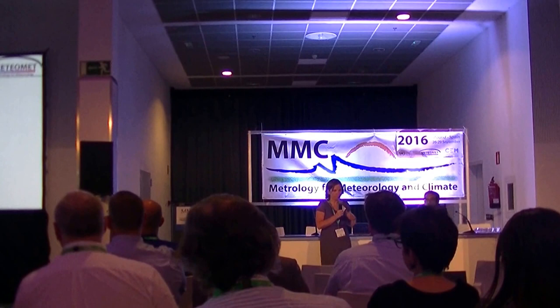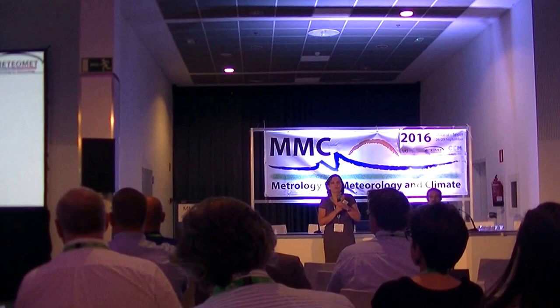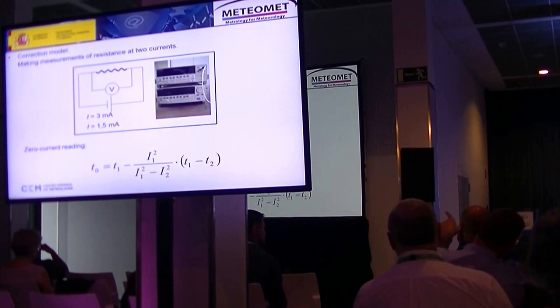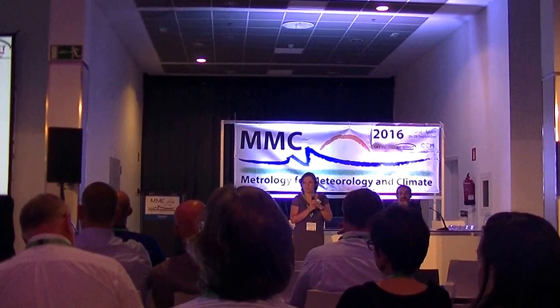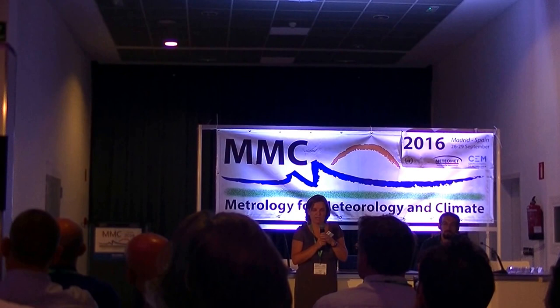The correction model used to evaluate the self-heating error is extrapolation by making measurements with two currents. We mainly performed measurements with two currents: 3 milliamps and 1.5 milliamps, measuring the voltage drop across the resistance with a nanovoltmeter.